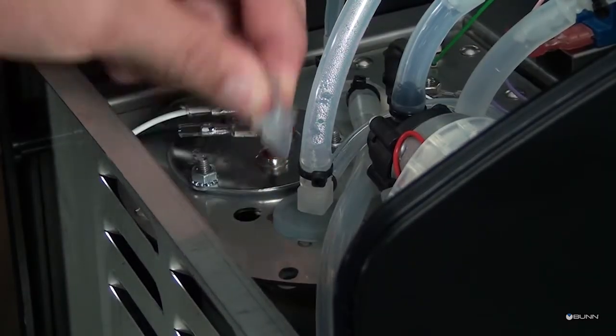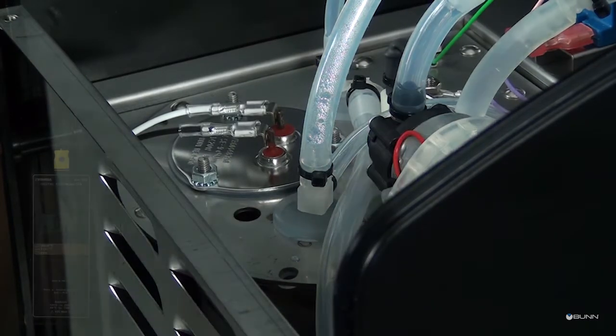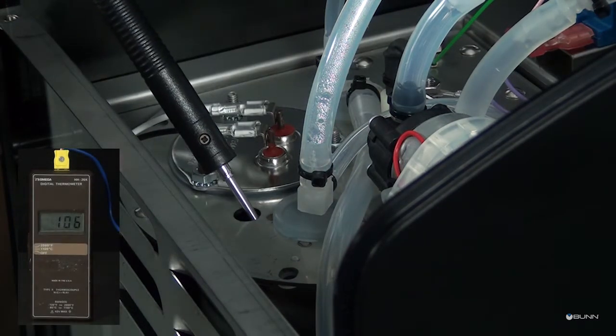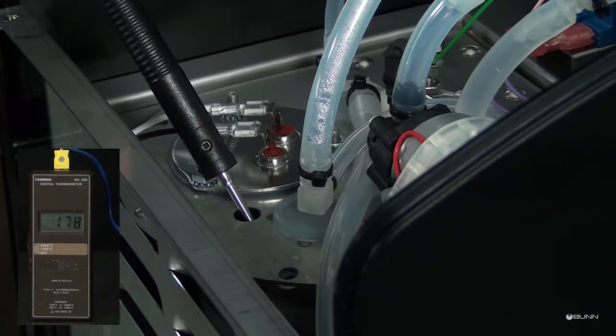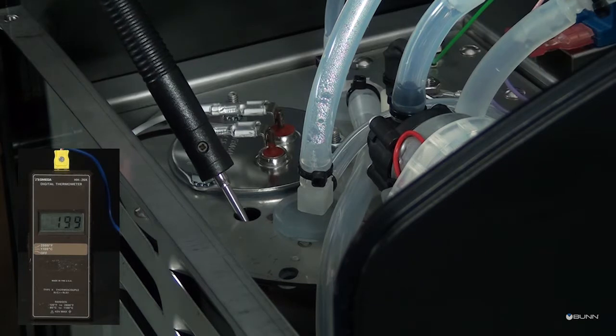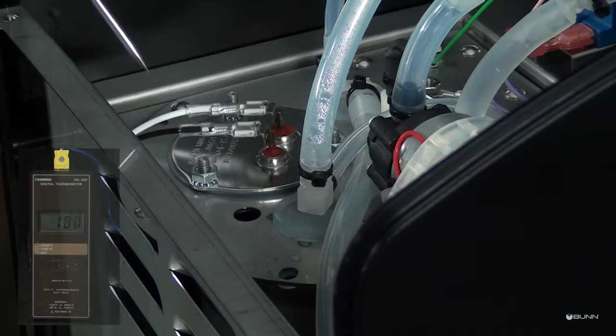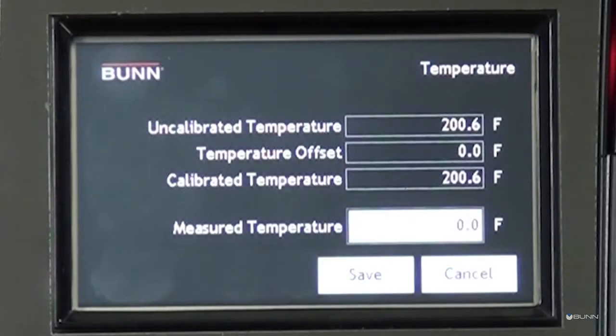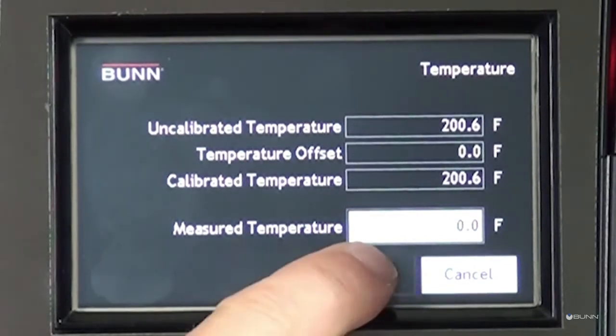Select temperature. Insert a known accurate temperature sensing probe through the tank lid plug to a depth of 6 inches. Enter the measured temperature in the white box. The uncalibrated temperature should be the old reading. Calibrated temperature should be equal to the measured temperature. Temperature offset should be the difference between the two.